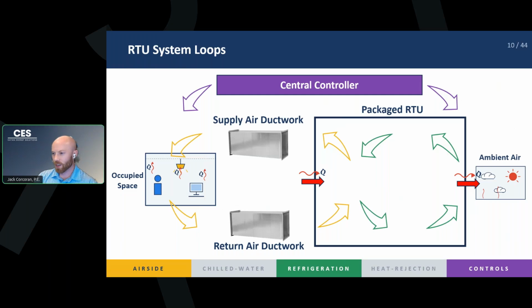Yeah, and so this is just another way of looking at it, right? We're still using our system loops that we had before. I drew a box around the refrigeration cycle, the refrigeration loop, and then part of the air side loop, right? Because that's all packaged within that box on the roof. And then, outside the box on the left side, we have the supply air ductwork and the return air ductwork going back and forth between your space and your rooftop. Nothing changes here, right? Our heat is moving from the left side all the way out to the right side.